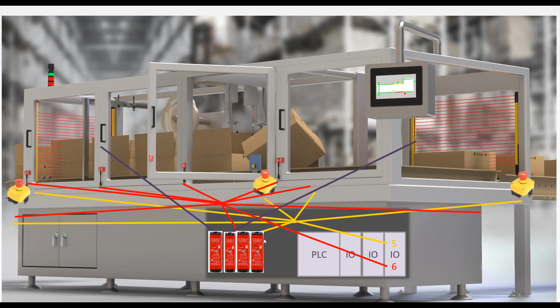So there's really 2 zones in this system. And what we do with our SC10 is we can get all the safety device inputs into it and tie them to zone 1. So both light curtains and the door switches are tied together and connected to safety output 1. And then the e-stops are connected to safety output 2, or zone 2.